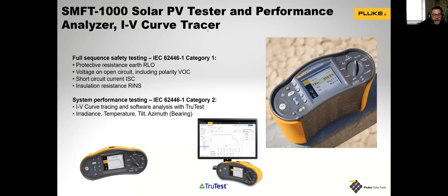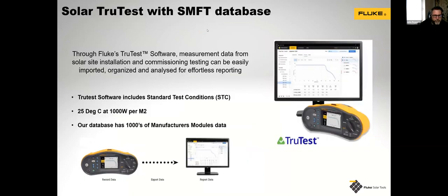we mentioned earlier, it'll give you irradiance at the solar panel itself, the temperature, and there's a thing you need to take into account when you measure the temperature of a solar panel, the tilt, and the bearing, which is basically where it is. So it's all about what is happening at the solar panel itself, because when you install a solar panel, everything around it may change. For instance, trees may grow, large buildings may be put up, and the efficiency that you had years ago may not be the same. And because we put these things in hopefully for a long time, because they do have a somewhat long payoff, you will be looking to make sure that it's providing an adequate amount of power.